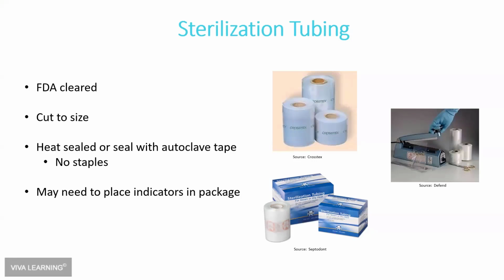You cut it to the size or the length of the instruments. You can buy it narrow or wide, whatever you need. And then you have a heat sealer that you use to seal the ends, or you can seal it with autoclave tape. But the one thing you don't do with these pouches is staple them, because that isn't an adequate seal. It'll fasten the end so the instruments won't fall out, but it won't seal it.